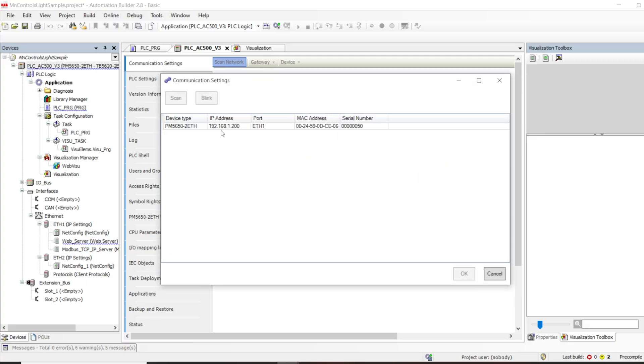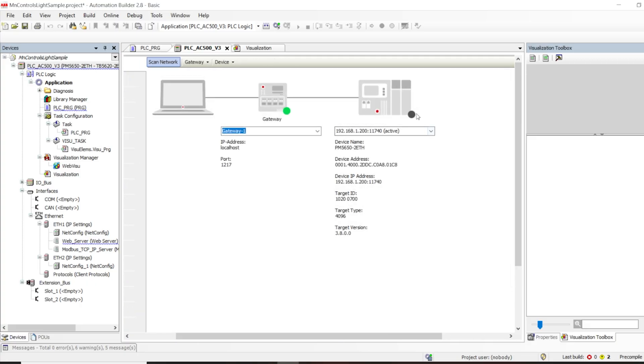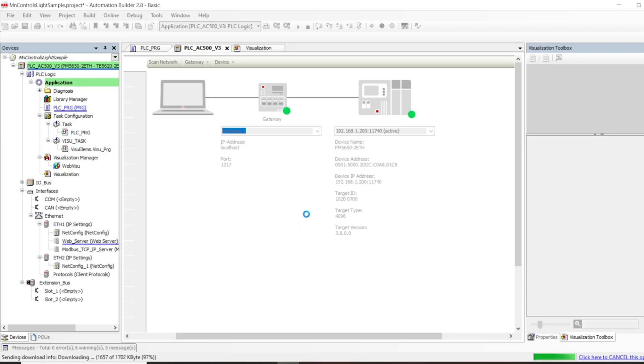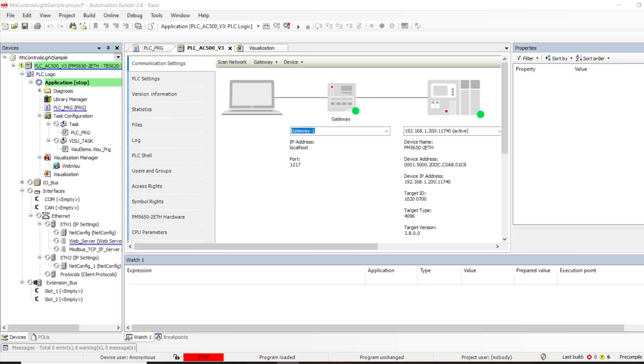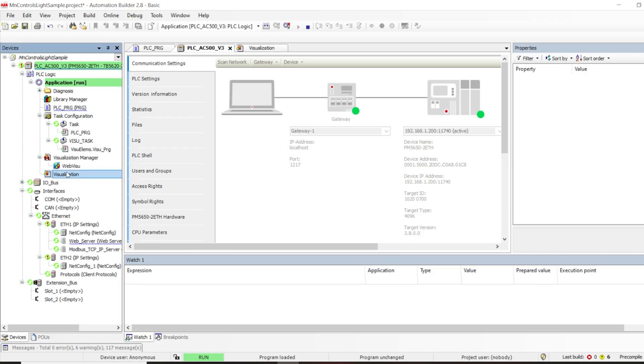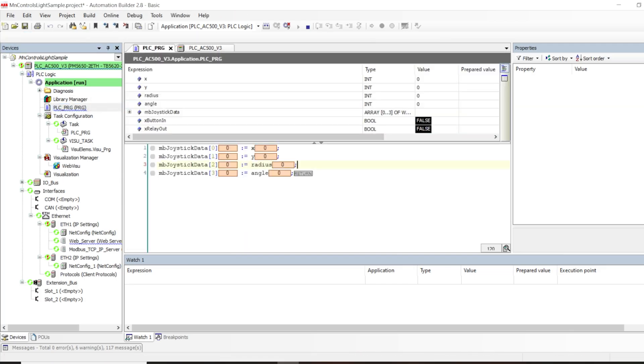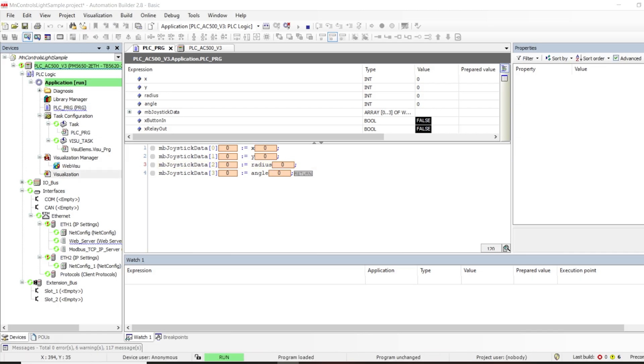I'll upload this code to my AC500 controller — I'll come here under Communication, scan my network, find my controller, connect, and upload the code. Now the Modbus TCP server is set up. I'll make a quick test to verify everything is working. As I move the joystick you can see I'm getting those values, and these are written directly to the server registers so we can access them over Modbus. This is working correctly.